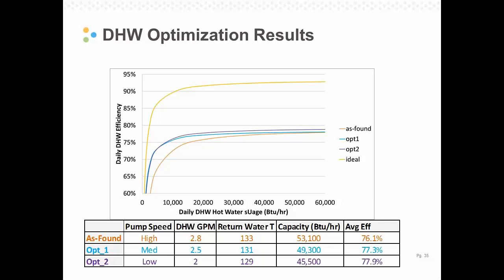Here are some summaries from some of the flow adjustments. You can see we were able to change the return water temperature some, but not super big changes. We got about 4 or 5 degrees, which resulted in a couple of percent DHW improvement, but nothing drastic. And this has a lot to do with the effectiveness of the heat exchanger in the indirect tank.